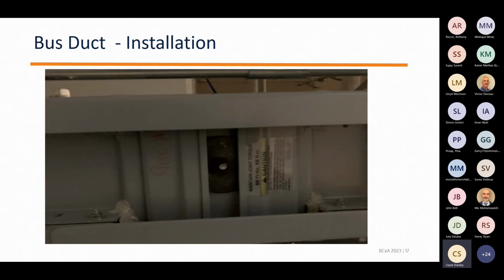This is a bus duct at a major facility. The bus duct was installed, and my electrician came to me and said we got a problem, that this duct was live in production and hadn't been clicked in. That's not good, that's quite concerning. He brought it up, and sometimes our facility people may be intimidated or bullied when they speak up about a problem they see. This is where our commissioning team needs support, to back up facility people when contractors don't want to play nice.